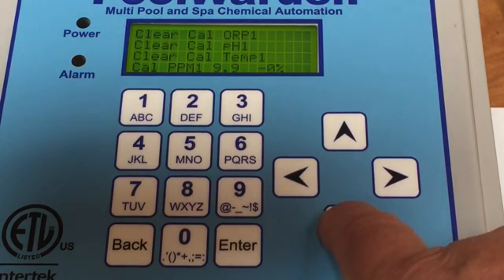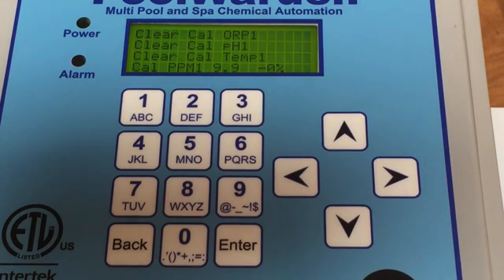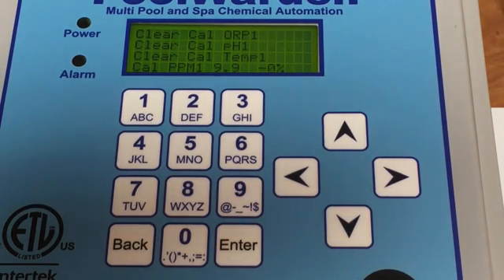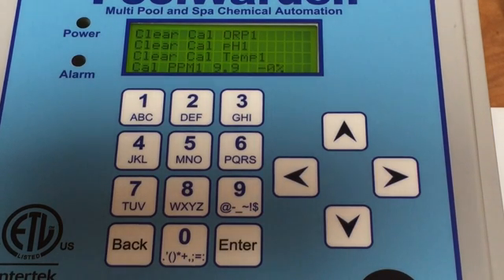You'll just have to let it go. If it goes through a cycle and then you see that it's not reading correctly, you can change that. But also, if you need to, you can just calibrate the ppm to what your hand kit says. It will store that reading and then adjust itself accordingly the next time it takes a DPD sample.